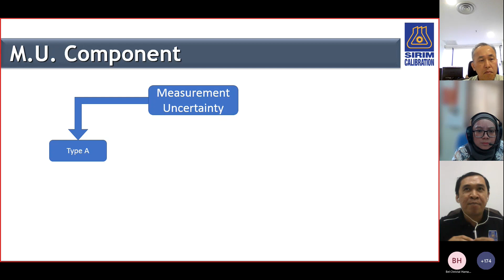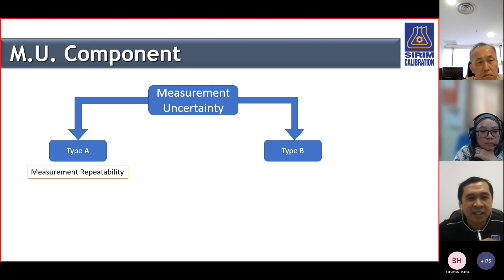Type A measurement uncertainty is measurement repeatability. This means that the measurement is taken 5 times, 10 times, and the more the better. Then after that, you calculate the average, and after the average, you calculate the standard deviation. That is type A measurement uncertainty, the one that we do for calibration.